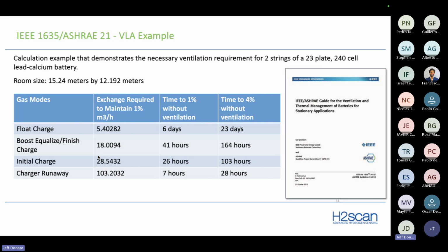And so in this case, they needed 5.4 cubic meters per hour to maintain just their float charge. Now, if they were to go to boost, equalize, or finish charge, then the number jumps up to 18. And so if you're just sizing for this particular room, you have to take into consideration this best and worst case scenario. Now, charger runaway obviously is very dramatic. It's a very rare condition.